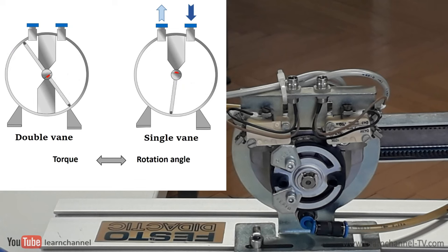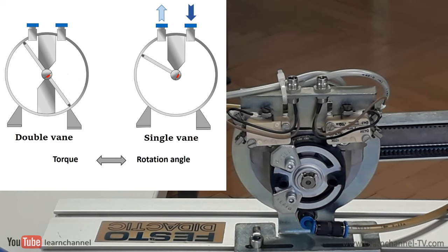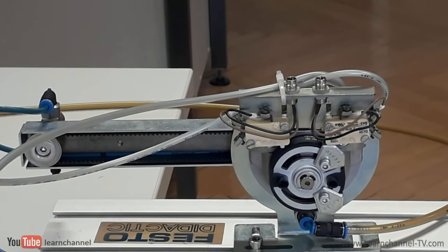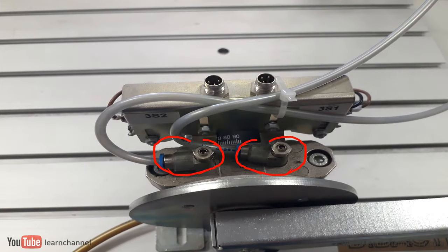The double-vane type offers a less rotational range, which is limited by half but produces twice the torque. This type of rotary cylinder uses external methods to limit the rotation or to cushion the load. The end position of our cylinder here is detected mechanically.